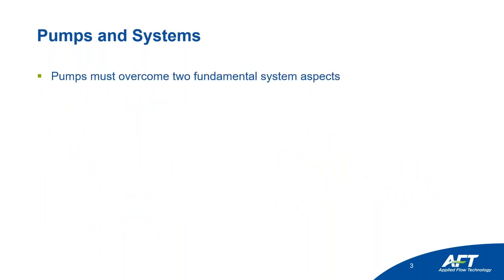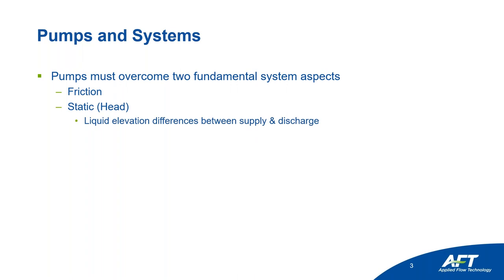So, pumping systems. A pump's job is to overcome frictional resistance as well as elevation changes in your piping systems. That's the job of a pump, to deliver flow and to overcome those two system aspects. One of the ways you can quantify the static head is simply the difference in elevation between supply and discharge tanks, or supply and discharge reservoirs.